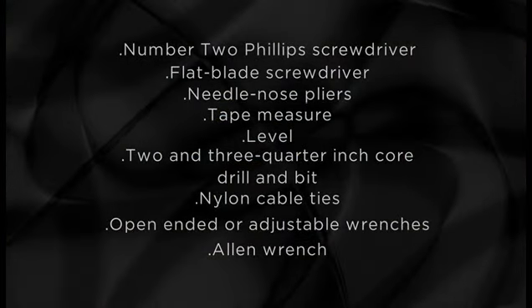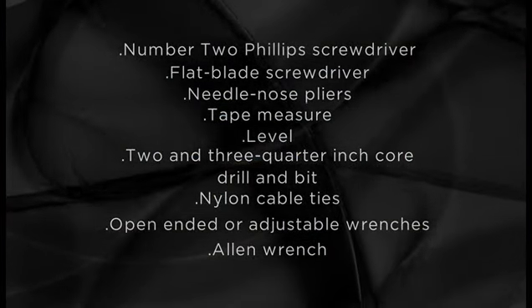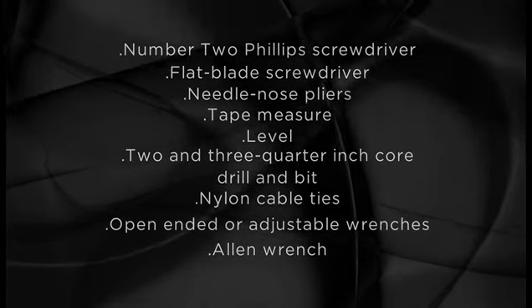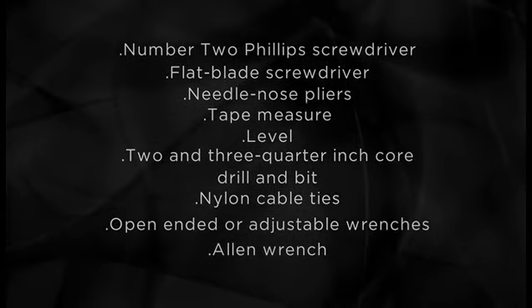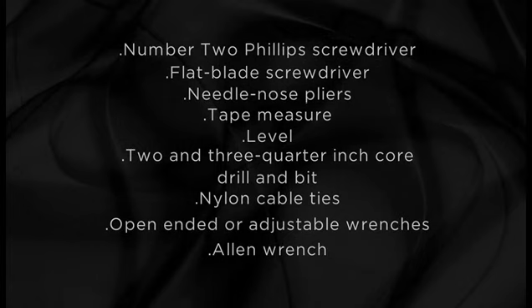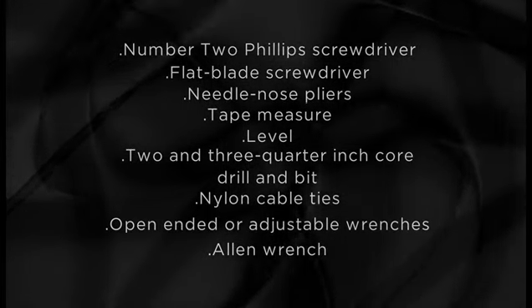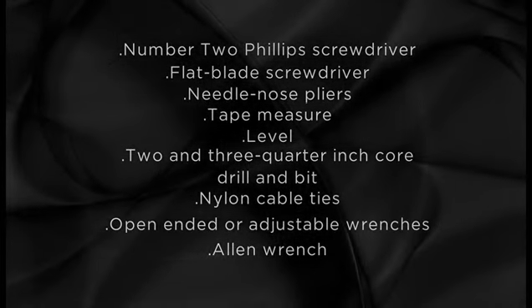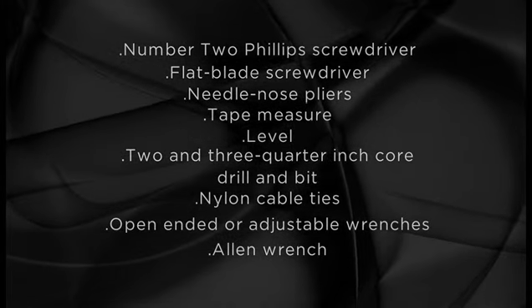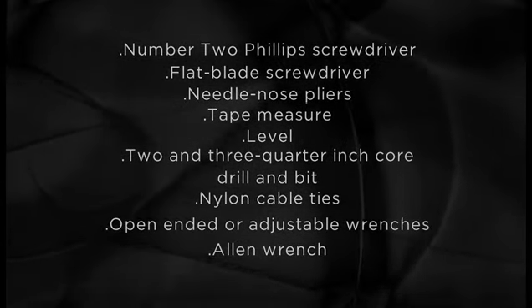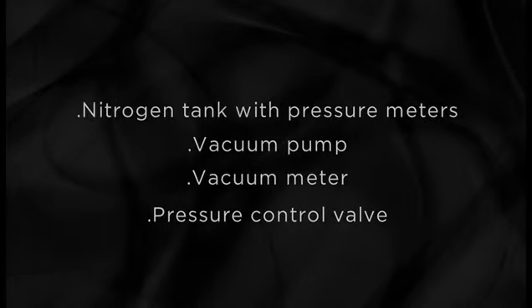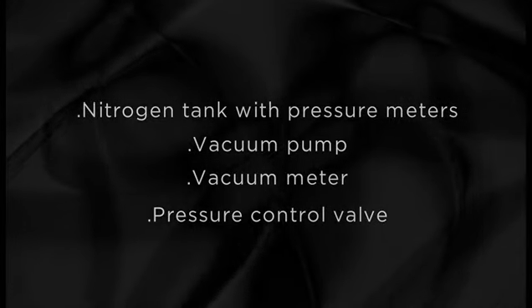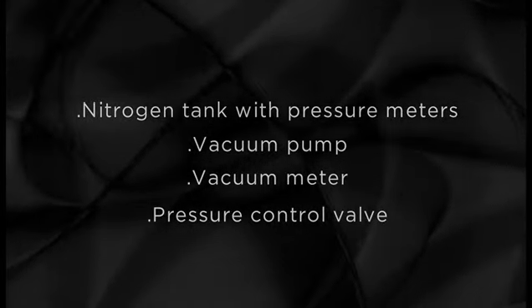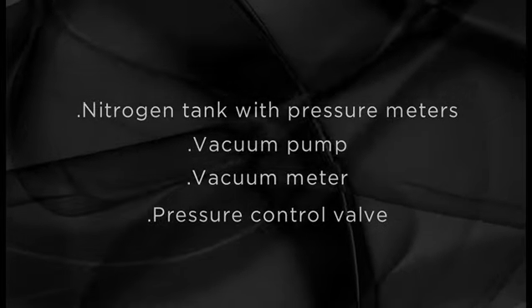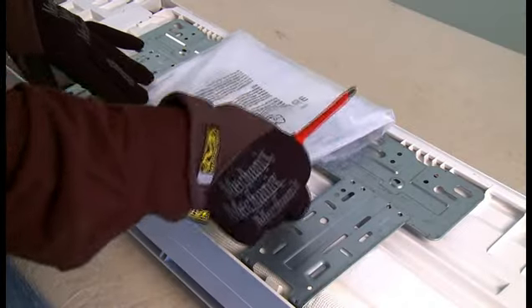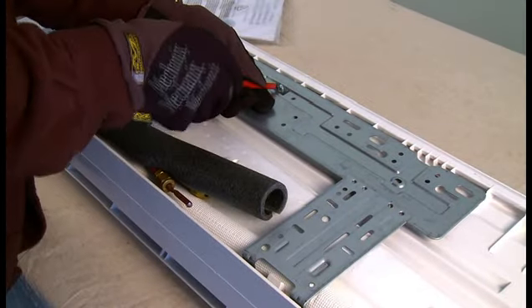To properly install the Frigidaire mini-split system, you'll need a number 2 Phillips screwdriver, a flat blade screwdriver, needle nose pliers, tape measure, a level, 2 3/4 inch core drill and bit, nylon cable ties, open-ended or adjustable wrenches, and an Allen wrench. Additional equipment includes a nitrogen tank with pressure meters, a vacuum pump, vacuum meter, and pressure control valve. We'll begin by preparing the interior unit for installation.